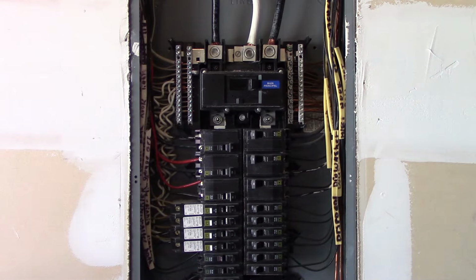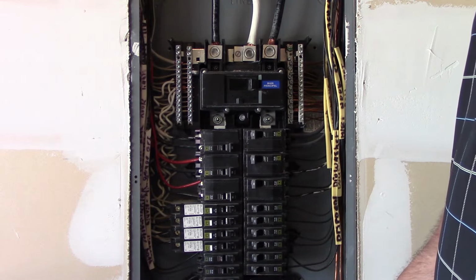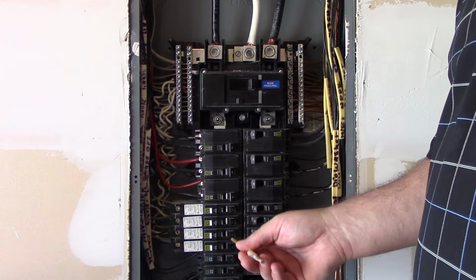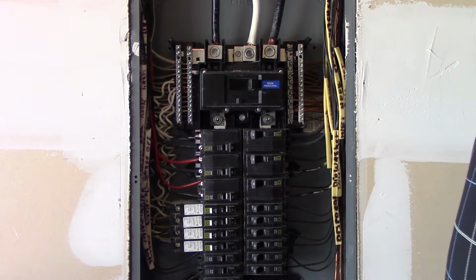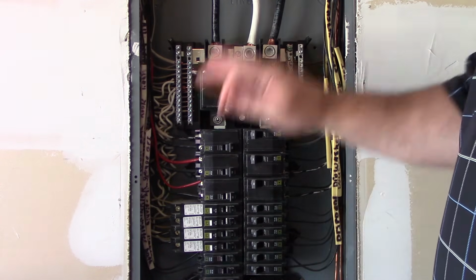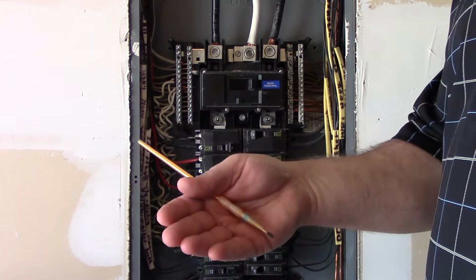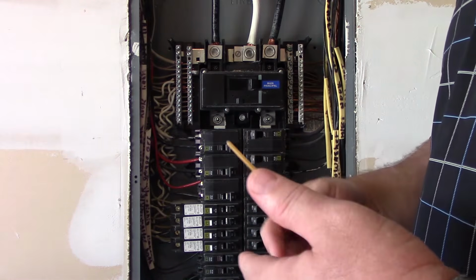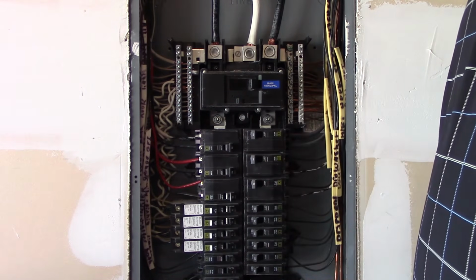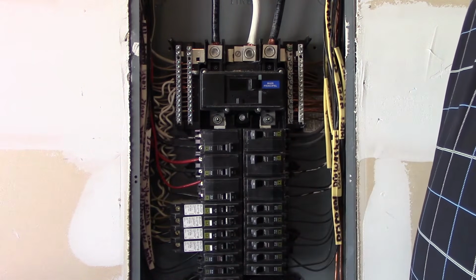Okay. Now, if this was a BR style or the Homeline version of Square D, then you might have a Siemens or a GE or whatever in here. And again, that is not listed for use in this panel. Okay. It's a different manufacturer. Now, they do make a list out there that will let you know which breakers can be used in which enclosure and on which panel board.